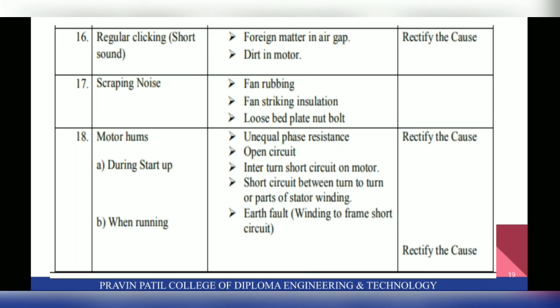Next trouble is motor hums, that is it produces some noise. First is during startup, and next is when running. Causes for these troubles are unequal phase resistance, open circuit, inter-turn short circuit on motor, short circuit between turn to turn or parts of stator winding. Next is earth fault, that is winding to frame short circuit. And possible suggested corrections for this are rectify the cause and find the solution for the suitable cause.